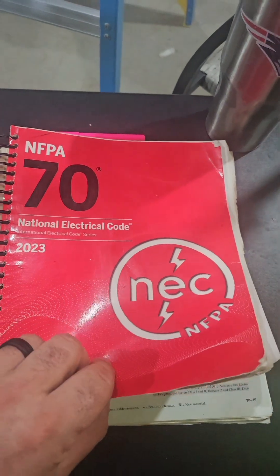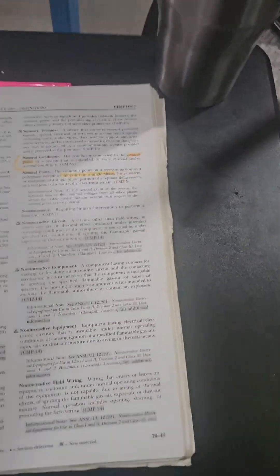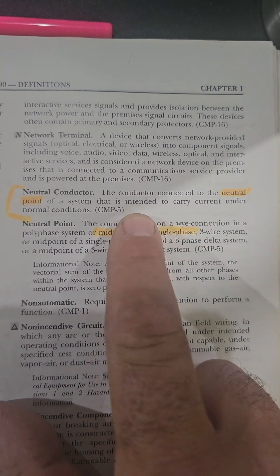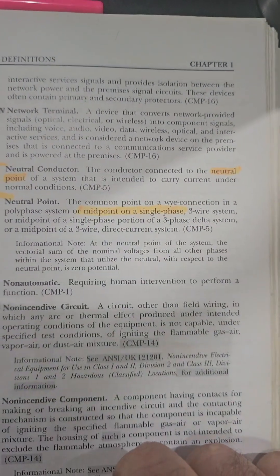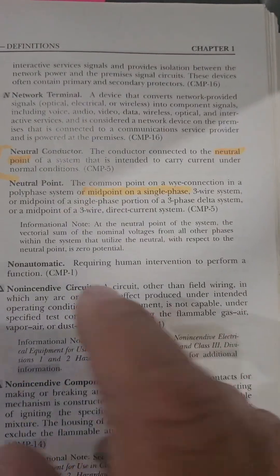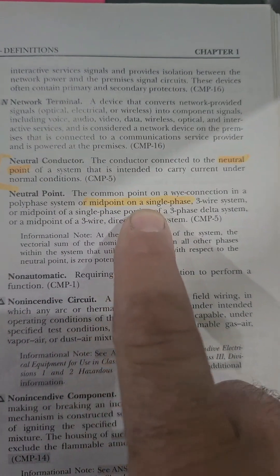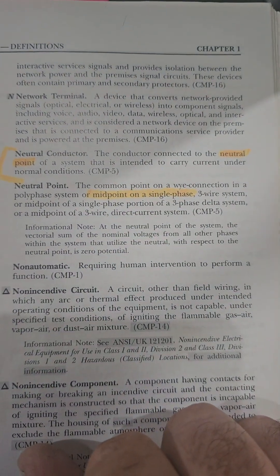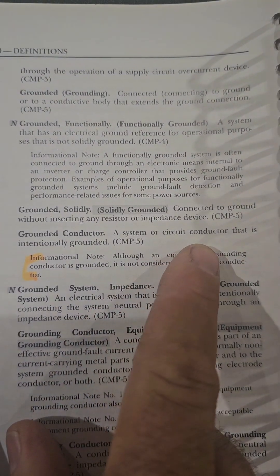2023 NEC definitions. Neutral conductor: the conductor connected to the neutral point of a system that is intended to carry current under normal conditions. The neutral point is the midpoint of a single-phase system. Grounded conductor: a system or circuit conductor that is intentionally grounded.